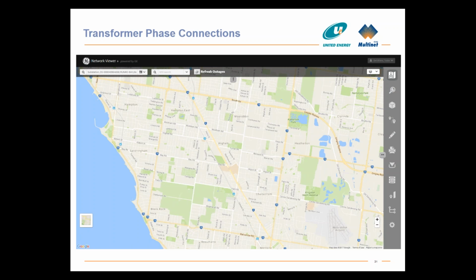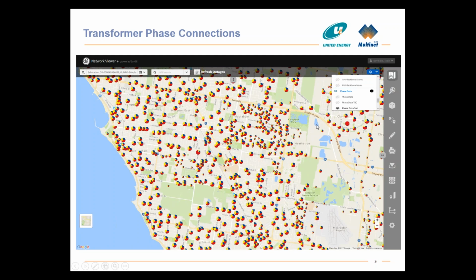Another big use case we're running with is identifying what phase every customer is connected to on the network, or for every load on a 3-phase customer, which of the 3 phases that load is connected to. Going to our spatial tool, under phase data, if we switch on the substations, we've created pie charts for all our transformers on the network so we can clearly see how well balanced they are.